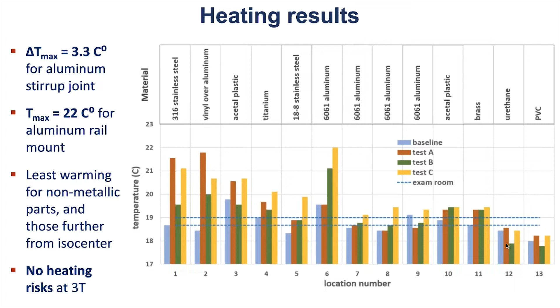The maximum temperature difference that we have measured was 3.3 degrees Celsius for location 2, which was the vinyl-covered aluminium stirrup joint. The overall maximum temperature that we have measured was for the aluminium rail mount, and it was 22 degrees Celsius, again just 3 degrees above the baseline, above the exam room temperature. The least warming was measured for the non-metallic parts, as expected, and those farther from isocenter. From these results, also from the fact that no heating was felt by placing a hand at these locations after the scans, we have deduced that there are no heating risks by using these hoverboard and stirrups in a 3 Tesla scanner.